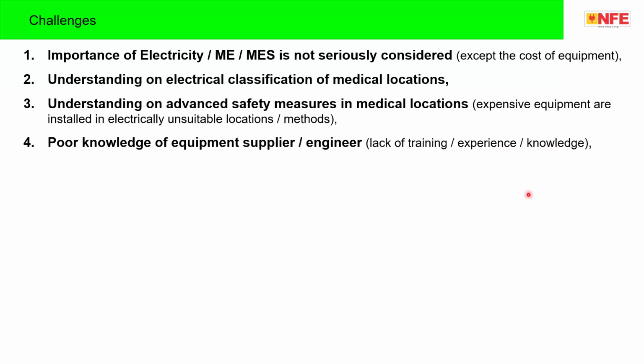One example we keep fighting against with equipment suppliers: most of them argue that 5 volt or 10 volt between neutral and earth is causing equipment failure. For example, a class 1 equipment is tested to withstand such measures, but they are not aware of this. So the lack of knowledge of the engineer is very critical.